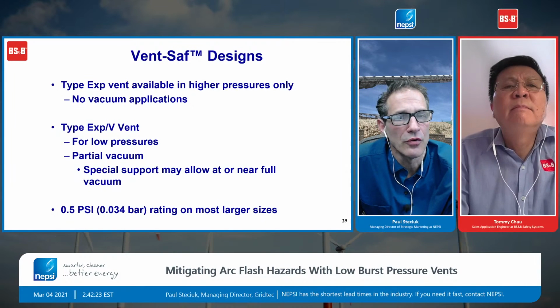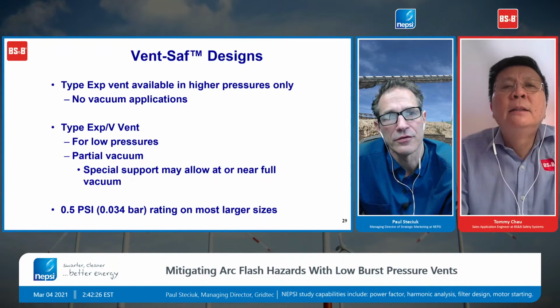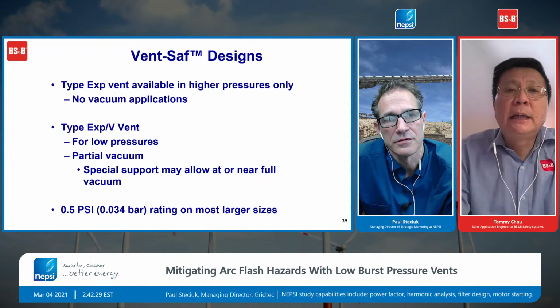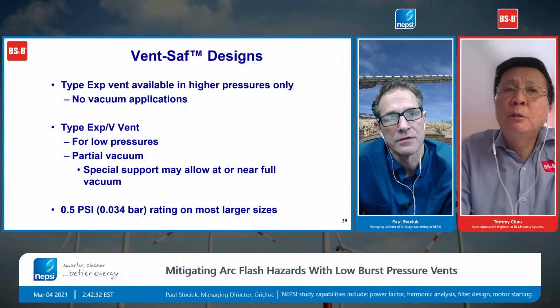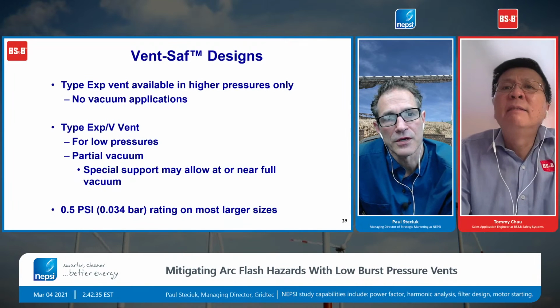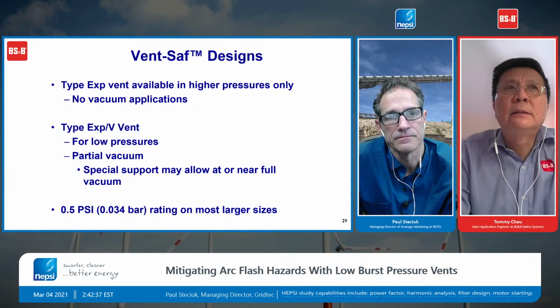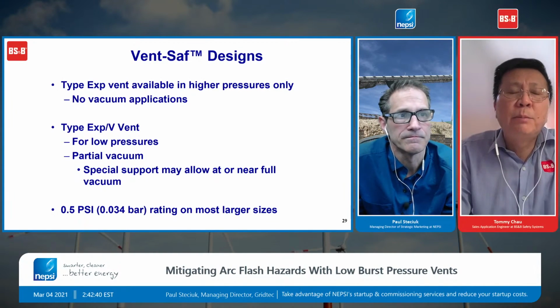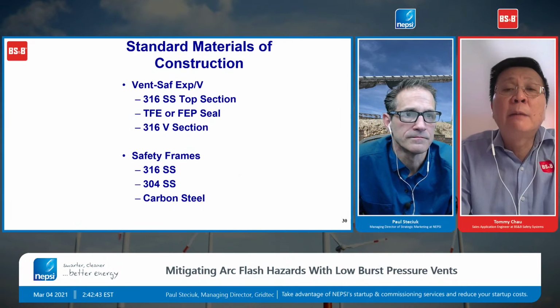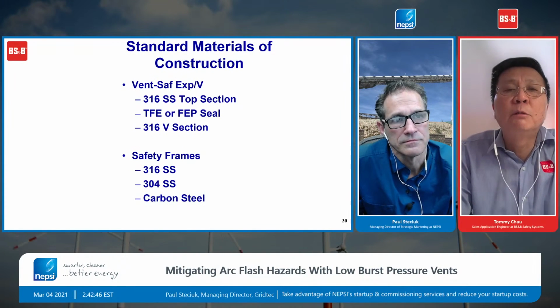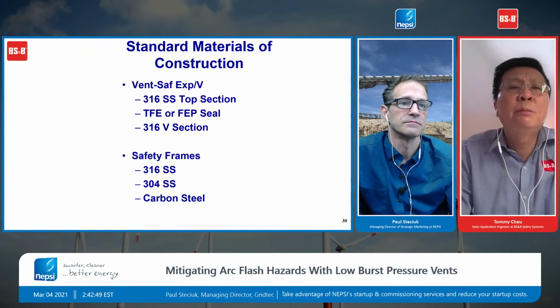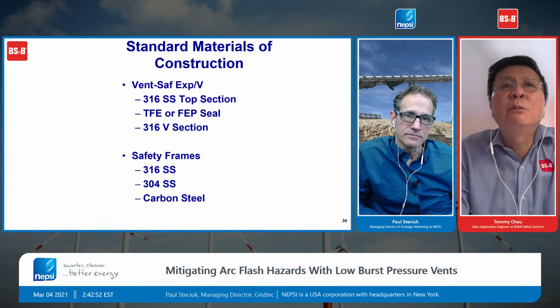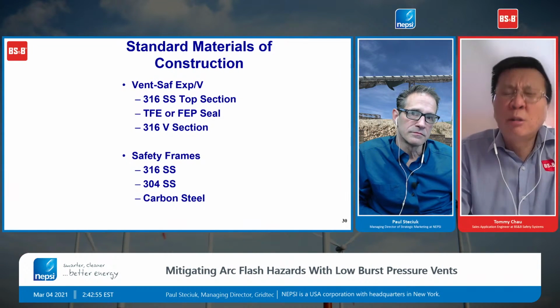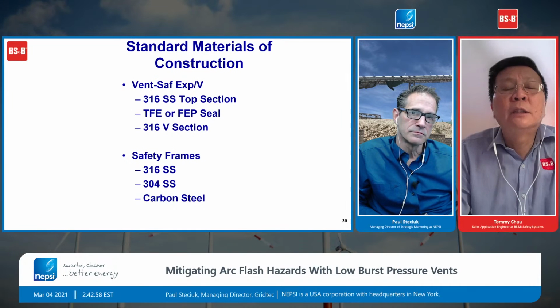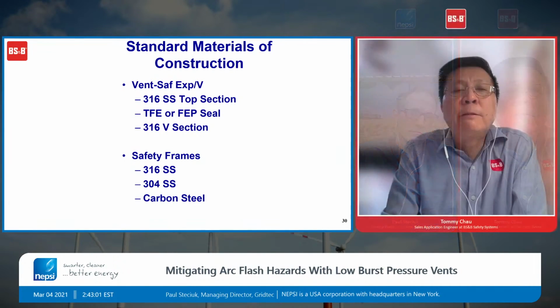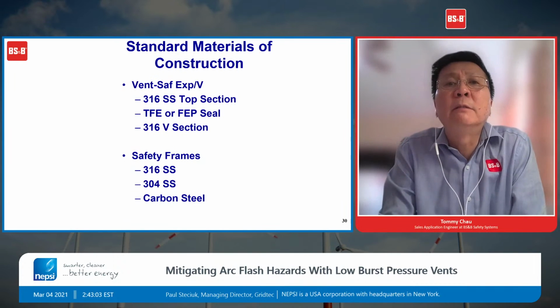Do you ever go lower, to 0.5 PSI? Is that the lowest? We have a building panel, Paul, that can go to about 0.2, 0.3 of a PSI. Okay, 0.2. 30 to 40 PSF, pounds per square foot. Yeah, so we do have a special building panel for really low pressure applications. Typically we use a lot of 316 material on explosion vents. 304 also is very common. And on the safety frame, carbon steel, 304 angle, 316 angle is very common material.